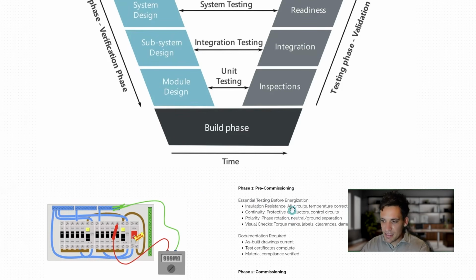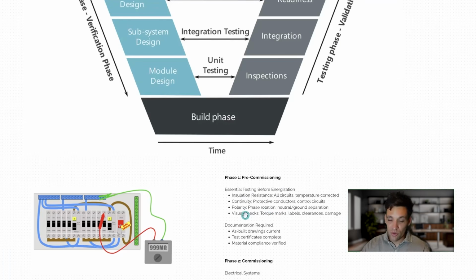So commissioning starts in the pre-commissioning phase, or also referred to as the construction quality assurance. This is where we test that everything has been installed correctly as per the design. So we do insulation resistance testing on cables, where we measure the resistance from the core of the cable to earth. We should get a very high rating, which means the cable has not been damaged anywhere. There's no nick on the insulation. There's no pathway to ground. So we're checking that the cable is safely insulated.